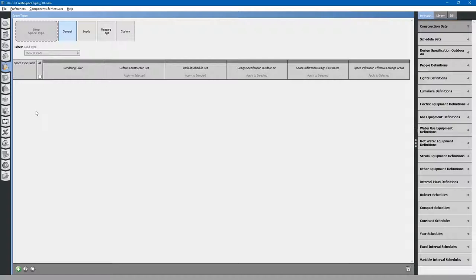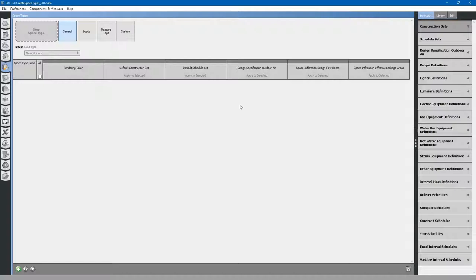EnergyPlus doesn't have space types, so you have to create each space separately in EnergyPlus. With OpenStudio, you can create a space type that has all of the information of the room: how many people are in the room during the day, electric lighting that gets turned on and off throughout the day, electrical plug loads, gas loads, infiltration, required ventilation rates for the room, and all manner of schedules that turn equipment on and off or show occupancy or activity levels.